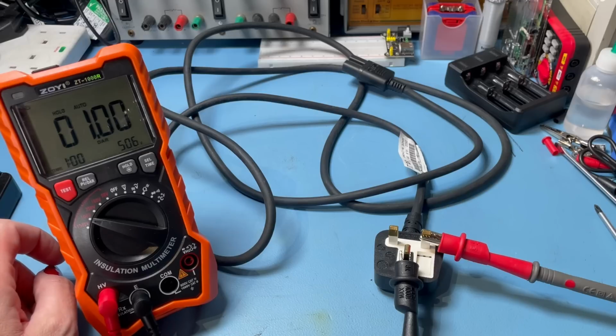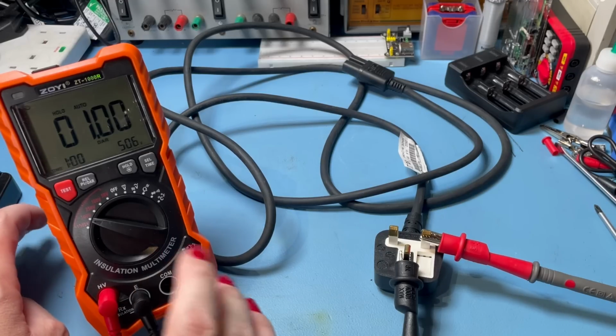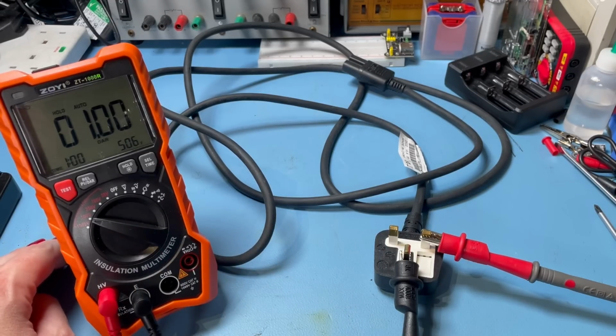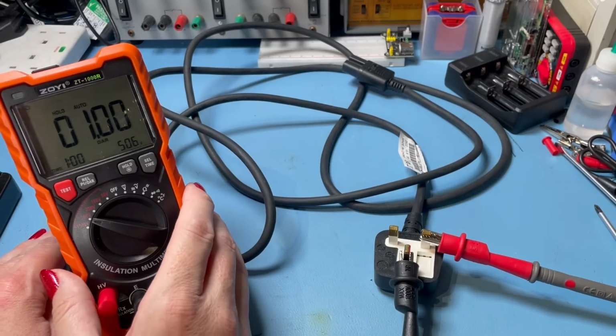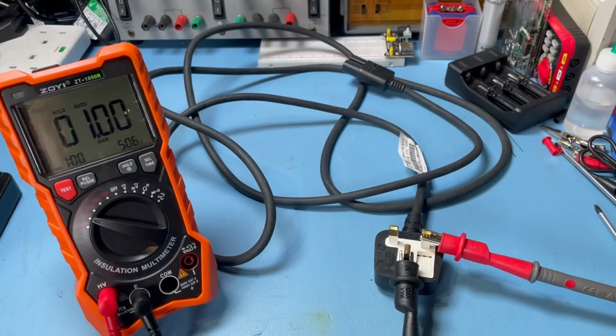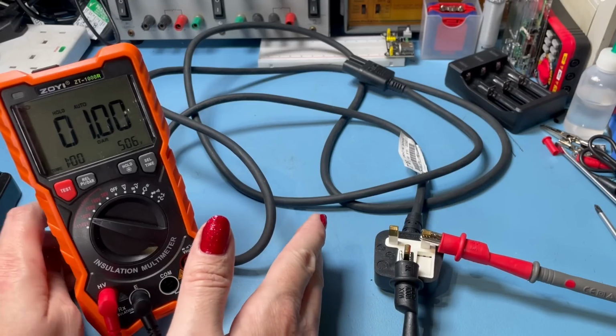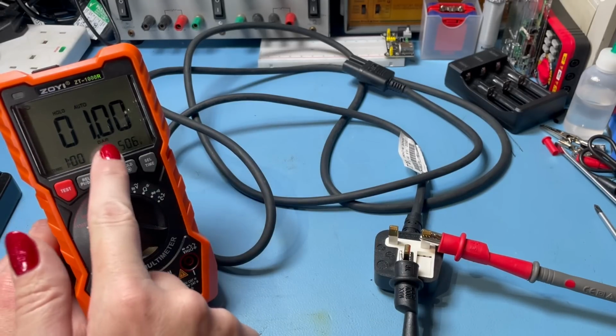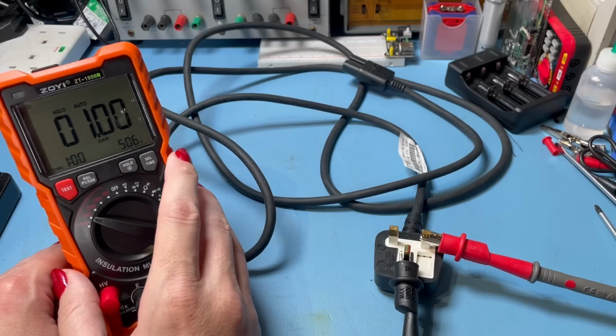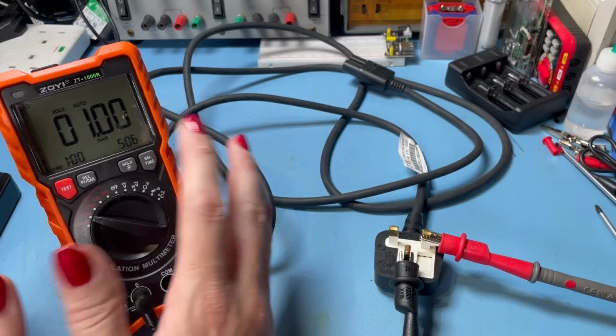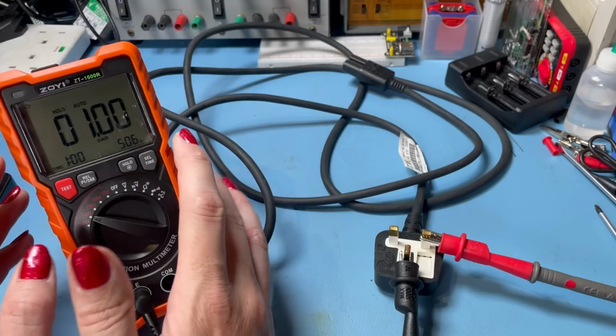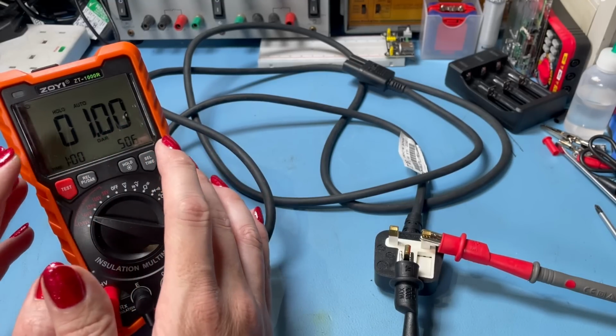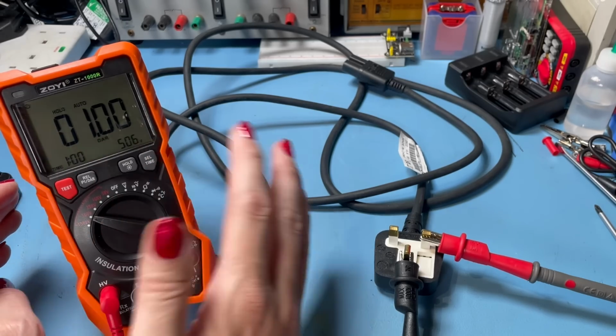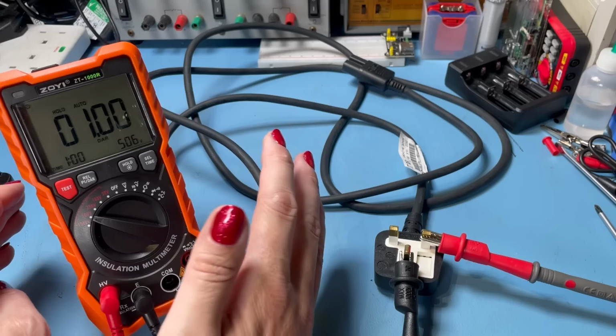You might notice there we didn't see any insulation resistance during that run. We just see overload. That's because the insulation resistance is better than 20 gigohms, so it's better than the meter can display. But where this is great on things like these kettle leads is it's going to give us that DAR reading. Now you also get the PI reading. The PI takes 10 minutes to complete and it's basically the same sort of thing. The DAR on this meter compares the reading at 15 seconds with the reading at 1 minute, whereas the PI compares the reading at 1 minute to 10 minutes.